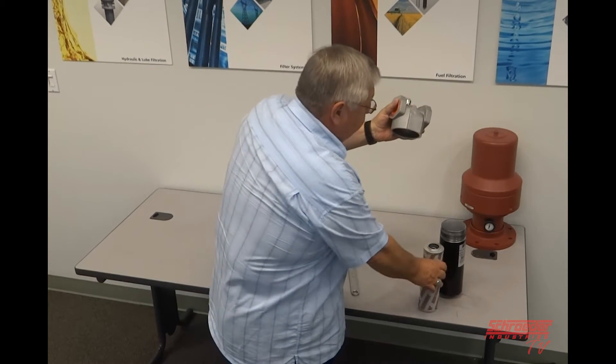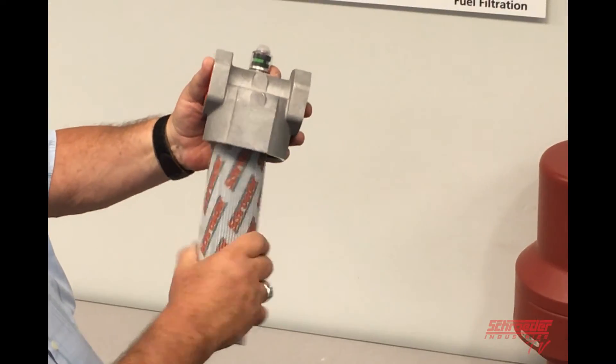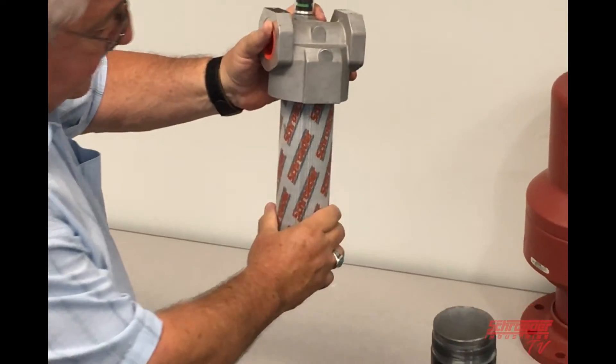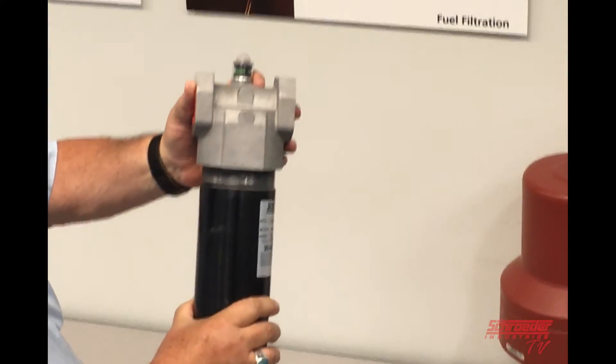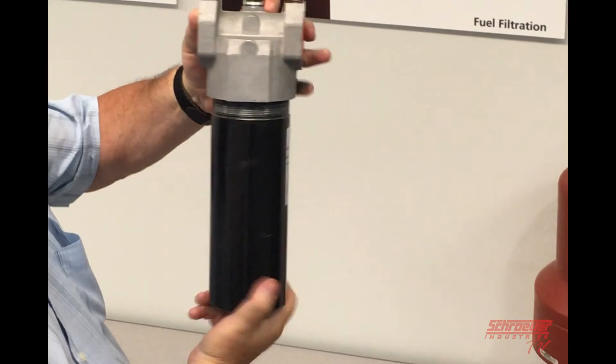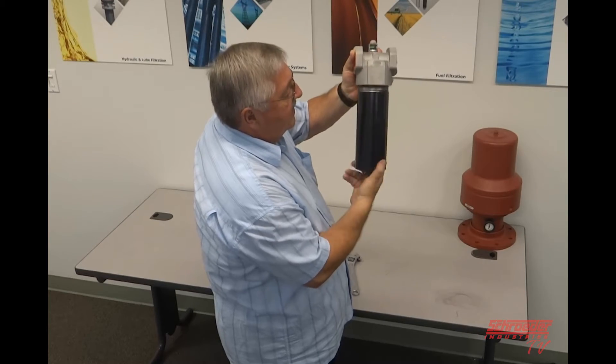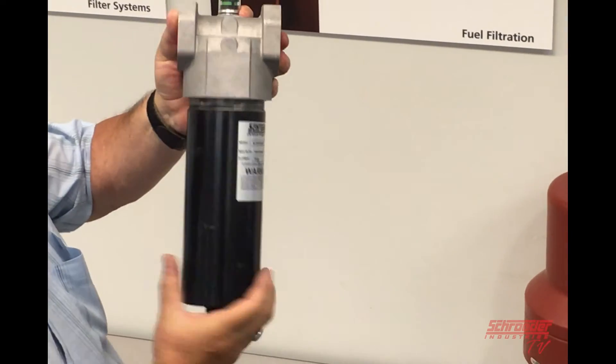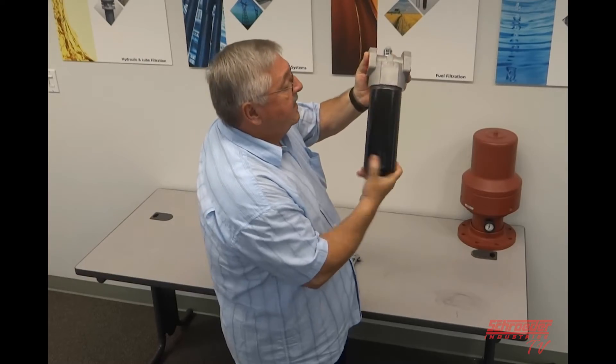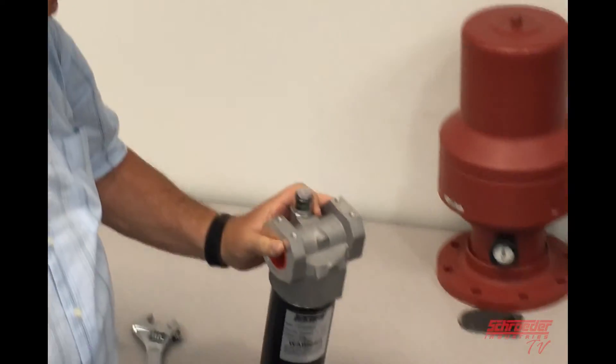You take your new element. Push it back up on the guide tube like that. Take your bowl and put it up inside. And just screw it back together. And take it all the way down until it stops. Put a wrench on it and take it about a quarter turn and it's sealed in place. And that's your element change. It's very simple.